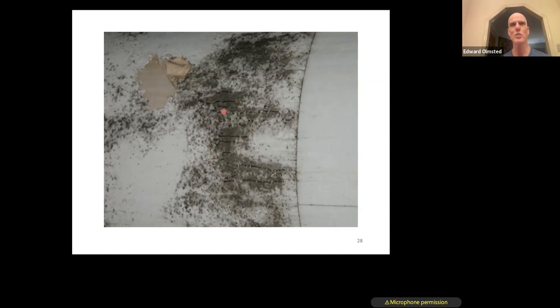I can tell you what's going to be growing here because I've looked at it enough. This is going to be a species that likes cold, really cold, because it's 40 degrees here. Once it gets wet and condensation starts happening, the insulation stops working, so the whole pipe starts to become 40 degrees, and that's what's growing there — a type of mold that loves it cold.